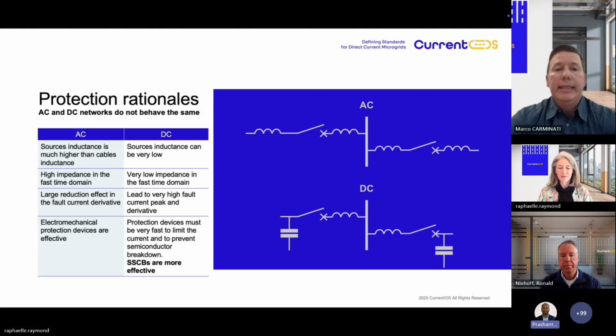Instead, if we have a DC distribution, as you can see, there are a lot of capacitances, which are the filter capacitances on DC side. And if we have, for example, a DC bus, like in this case, we can have more than one capacitance in parallel. So in case of a DC fault, we can have a very, very huge current peak according to the ratio between the inductance and the capacitance in our system. But in this case, the current derivative is very, very high. So there is the risk that the traditional circuit breakers are not able neither to detect nor to interrupt the short circuit current. So in this case, solid-state circuit breakers are more effective than the traditional.